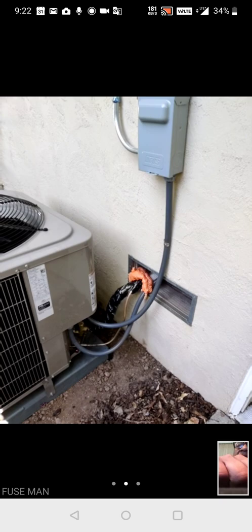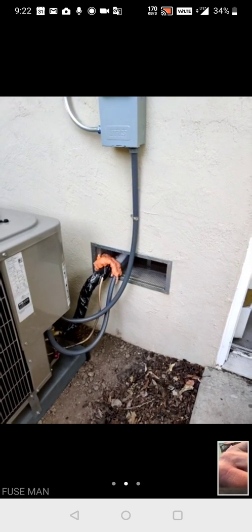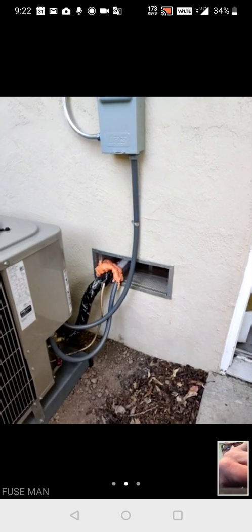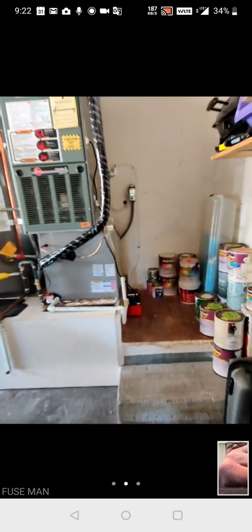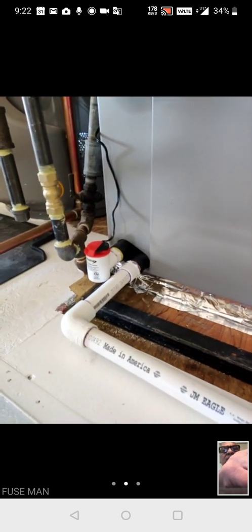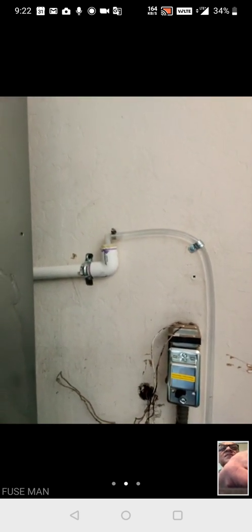Show me the vent down here to the left. You foamed the opening — so how am I going to see the supports for the line set? Show me where the condensate goes. The condensate runs this way to a drain pump, then the drain pump goes to a PVC pipe, which runs behind the furnace and the water heater, and then goes to the sewerage. There's enough gap — more than one inch. I'm good with that.